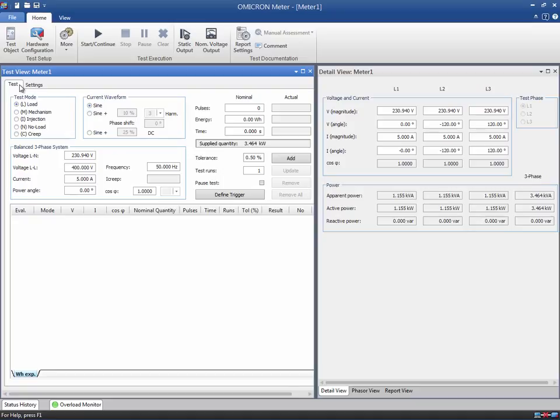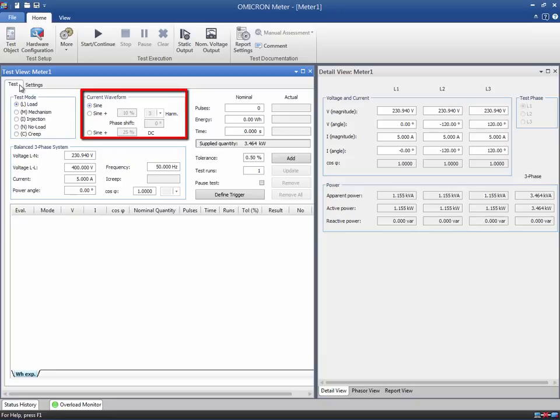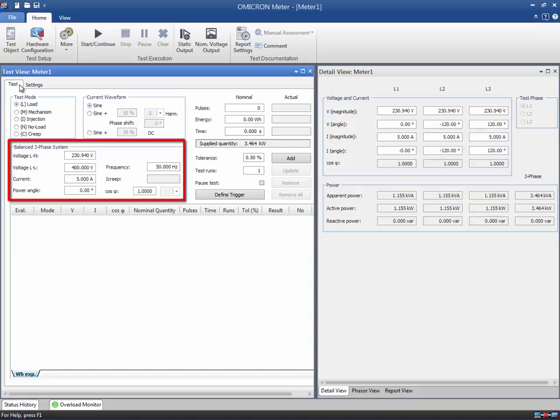In this test, we will output a pure sinusoidal current. Other current waveforms are available for testing the behavior of meters with harmonics or DC components. For a balanced three-phase system, you can specify the values of voltage, current, power angle, and frequency. Note that the power angle has been set to zero since we will test the measured active power according to our definition in the test object.